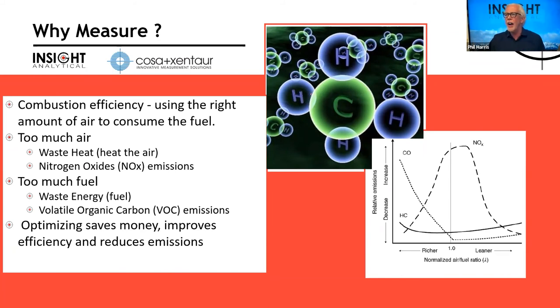And not only that, but if we put too much air into the burner, we end up increasing the amount of NOx emissions that we create. And NOx is a priority pollutant. It's a monitored pollutant. We want to reduce ambient levels of NOx in the environment. And so we want to try to optimize that burner to keep our NOx emissions as low as possible while getting the most energy out of the fuel.